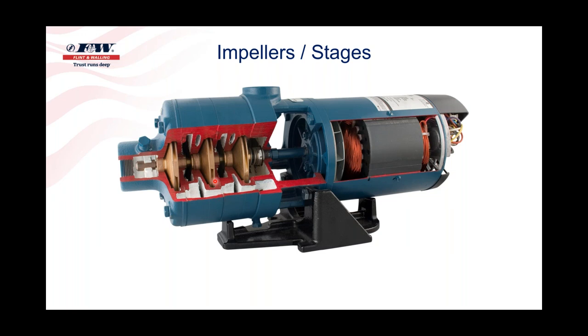I go, "What's going on with the impellers?" He said, "Well, I take the pumps apart. They're just all in shreds." I said, "So the plastic impellers are shredding." He goes, "Yeah." And I said, "Well, there's something causing that." He goes, "Well, I know exactly what's causing that." I said, "What is it?" He said, "Shells." I said, "Like seashells." He goes, "Yes." I said, "Those are getting inside the pump." He goes, "Absolutely." I said, "Well, let me ask you a question."